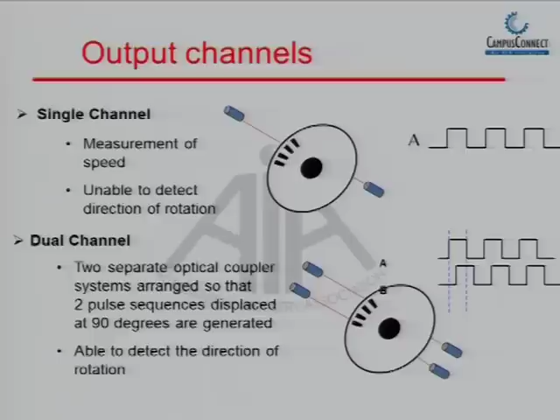Every encoder may have these two channels plus a zero channel, which we call the home channel. Right? This is the marker pulse or the zero position pulse, and these are the two channels based on the number of pulses. For clockwise or anti-clockwise, we require both these channels at a phase shift of 90 degrees. For homing, in case of power failure, either you have to go to a mechanical stopper or you have to rotate the encoder to a position where you get the third channel pulse. This is known as the zero channel pulse.